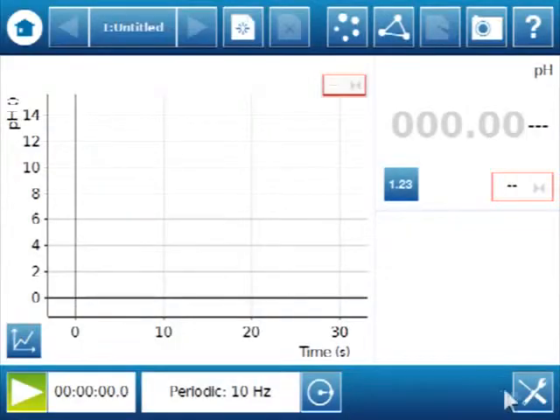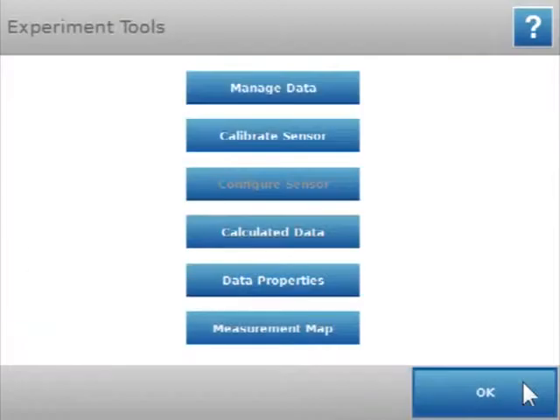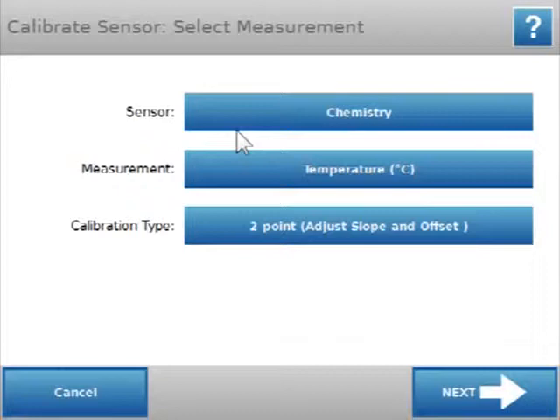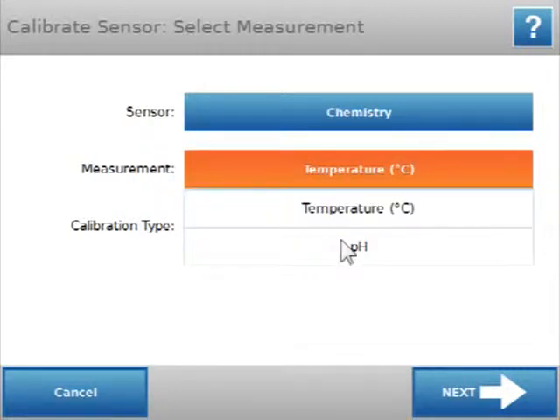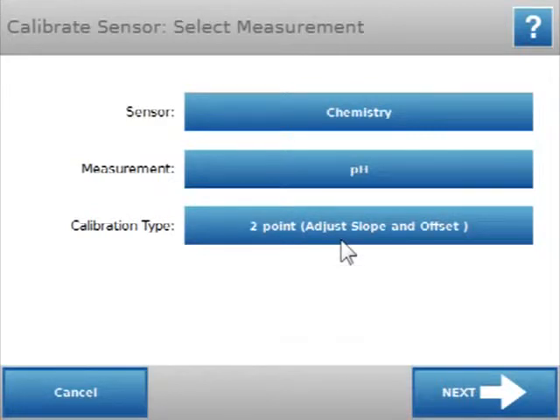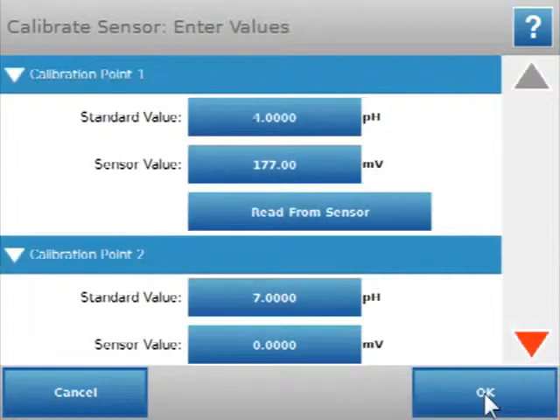I'm going to go down to the tools in the lower right-hand corner here, and that is where I'll find the calibrate option. So let's select that. You'll see it shows that I have the chemistry sensor connected. The measurement that comes up by default is temperature. We want pH, so I'm going to touch on that to select pH. And you see it's already set up for a 2-point calibration. That's what we want to use with the pH sensor. So I will say next.